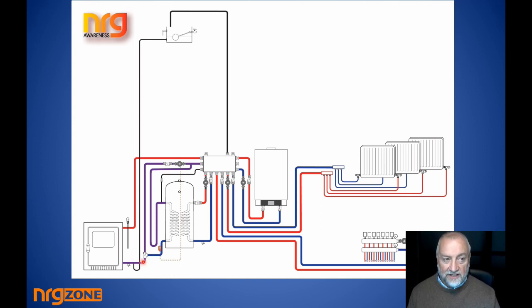That injector T will allow for the water to go in the middle unobstructed and back to the stove. But there's a little spigot sticking out here that if this pump turns on, it fires water past the center connection. Using a principle called the Bernoulli effect, it sucks water back out of the center connection, so it assists the gravity circuit, and at the same time it fires the water from the manifold, from the energy zone, down through the injector T and into the stove. That picks up excess heat, and then the radiators will have water.